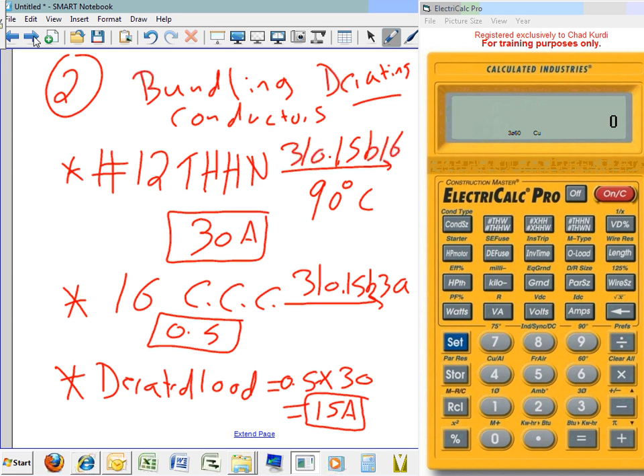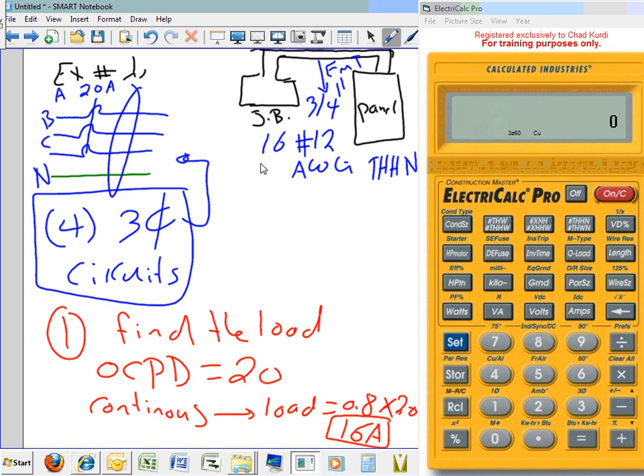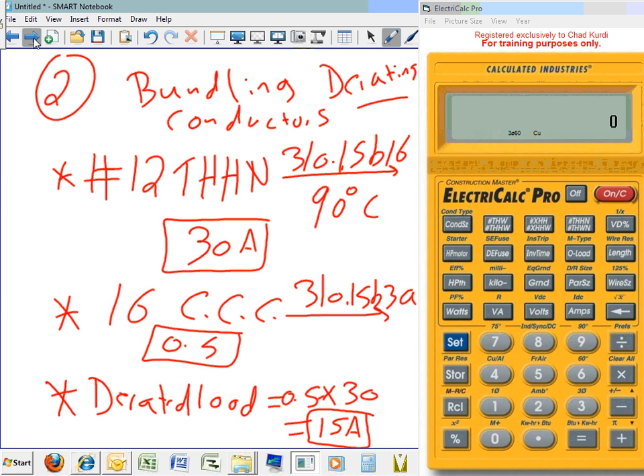If I want to stick with the 16, let's do it based on the 16. Remember, no matter what I do out of this design, I can't carry more than 16. So I know what my load is. I will start with my load. My load is what? 16, no matter what. So let me just go tell the calculator: size me a conductor that's going to carry 16 amps if I bundle 16 of them in one conduit. And then I'm going to ask the calculator again to do 15 amps to see if we can get up. Now, Phil, my friend, if I ask my calculator right now to give me 15 amps, what do you think the answer should be?